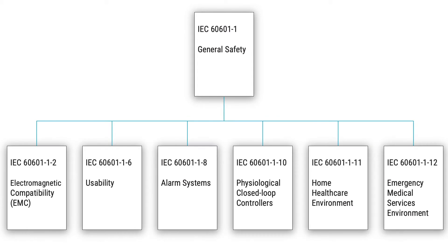The general standard relevant for safety for electrical medical devices is IEC 60601-1. This standard specifies general requirements for basic safety and essential performance. The general standard is an umbrella standard based on collateral standards and particular standards. The collateral standards specify general requirements applicable to subgroups of devices as well as specific characteristics of devices not covered by the general standard. The topics of the collateral standards include electromagnetic compatibility, usability, alarms, closed-loop controllers, home healthcare and EMS. In principle, each of these collateral standards apply in parallel with the general standard.